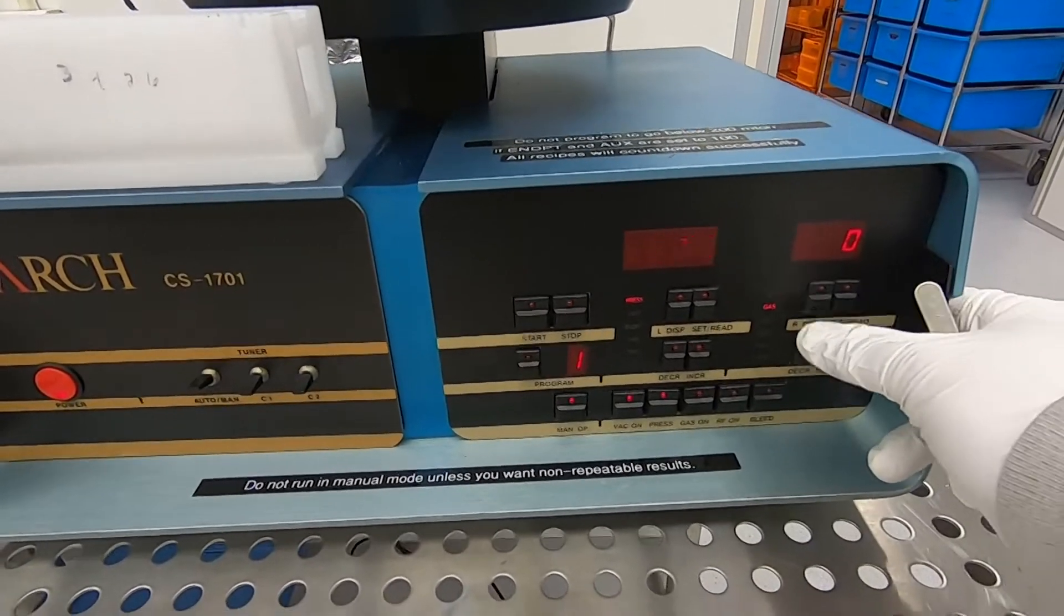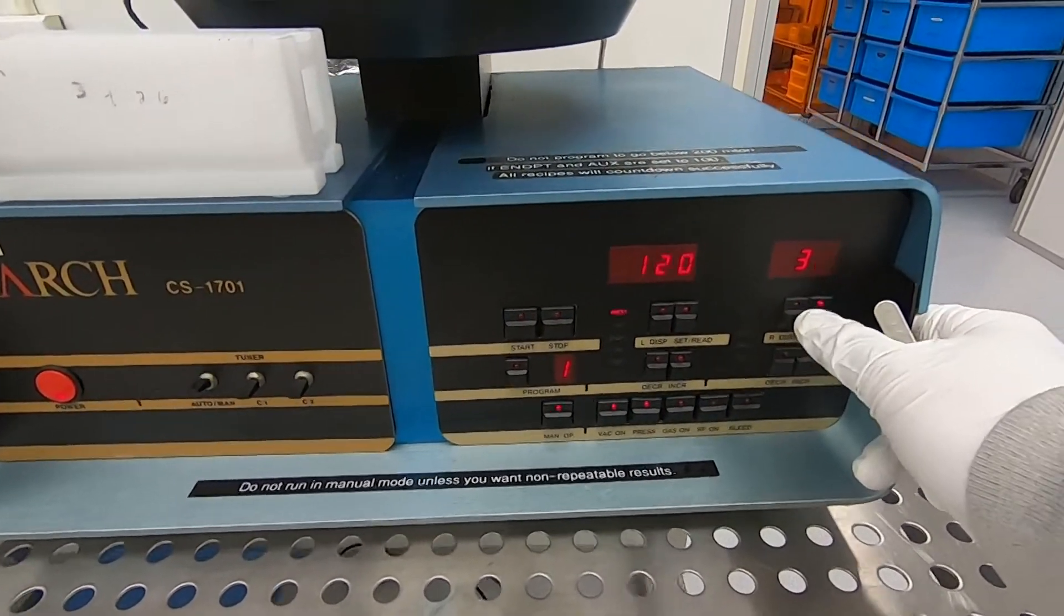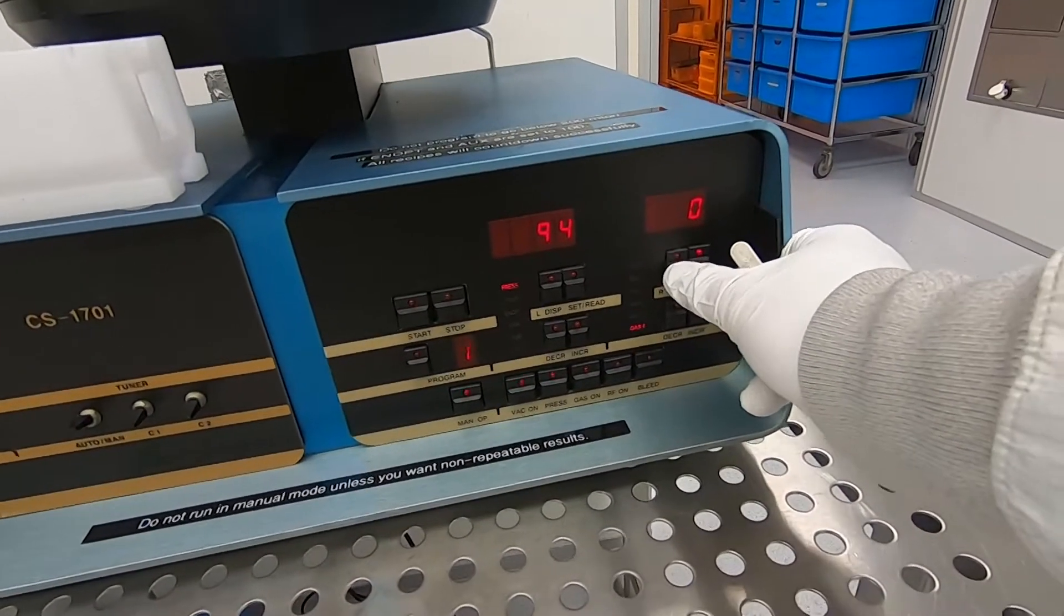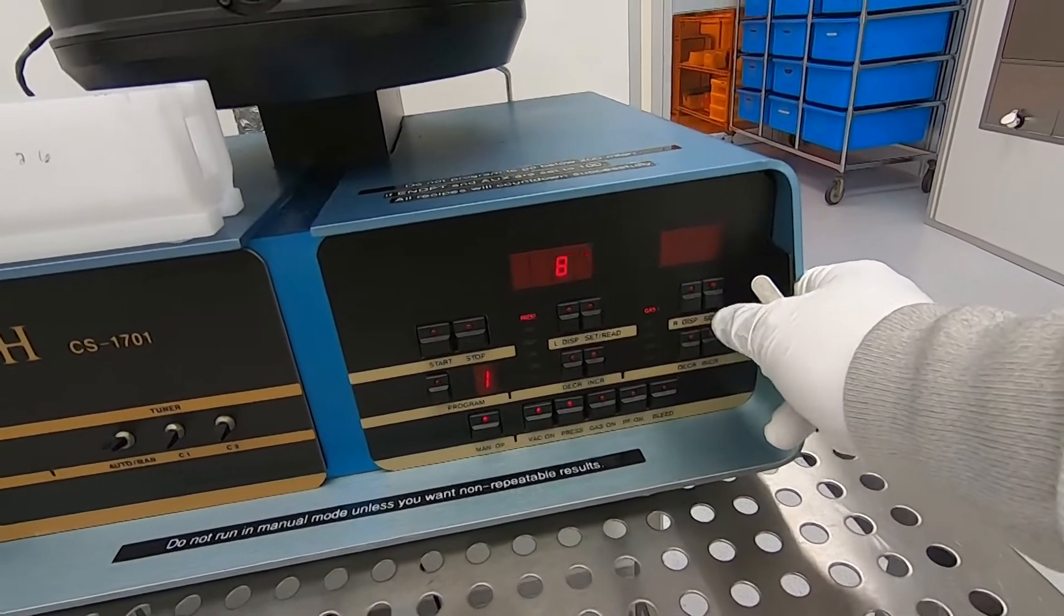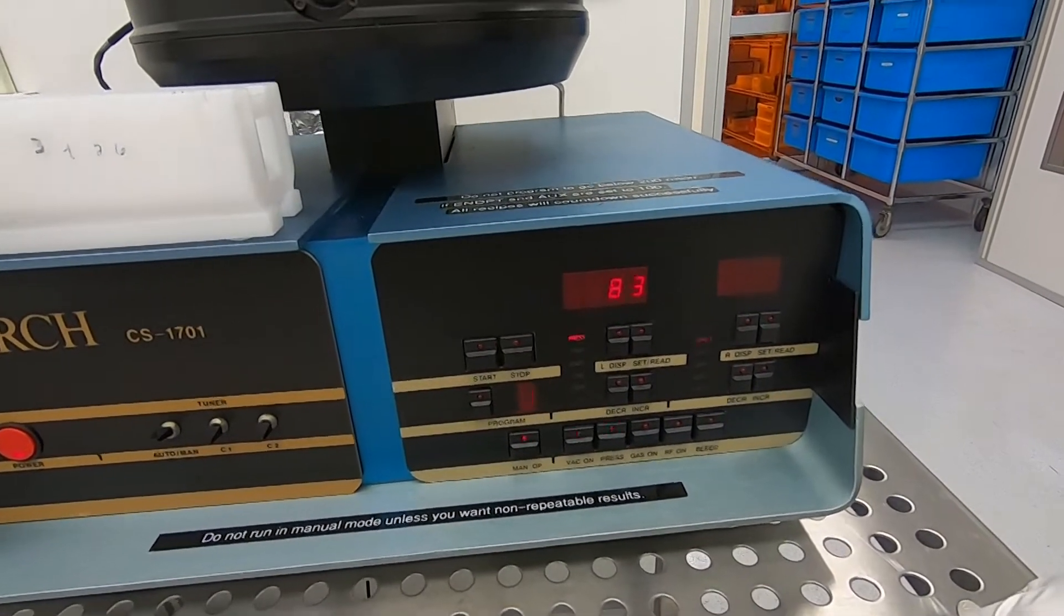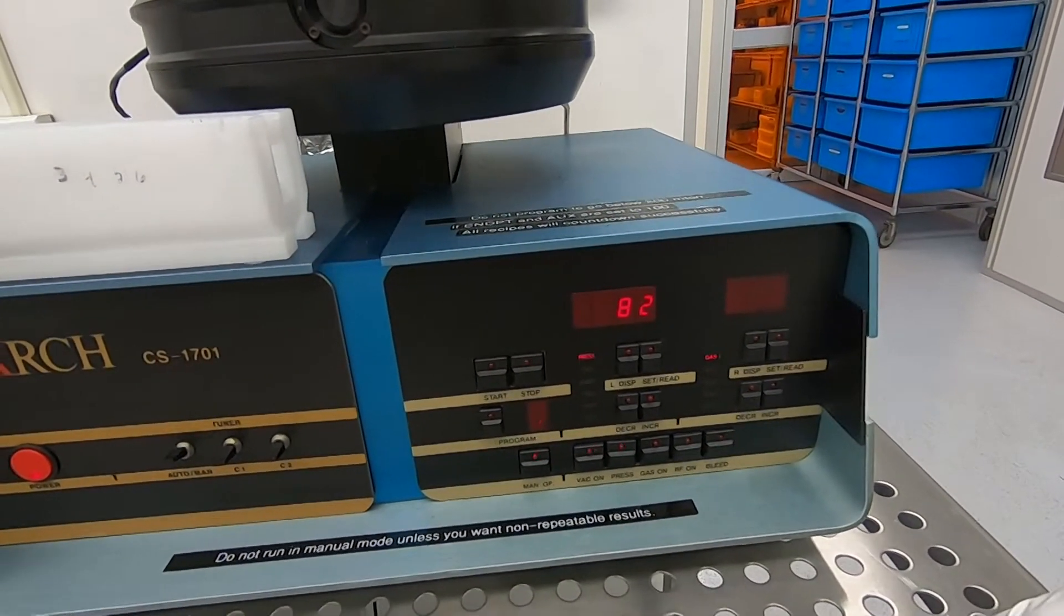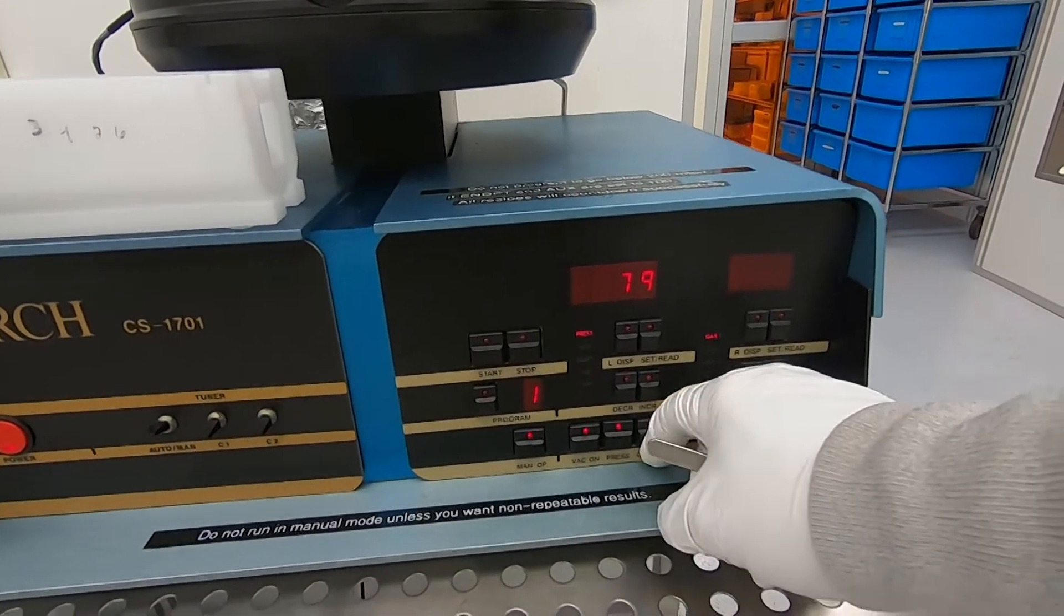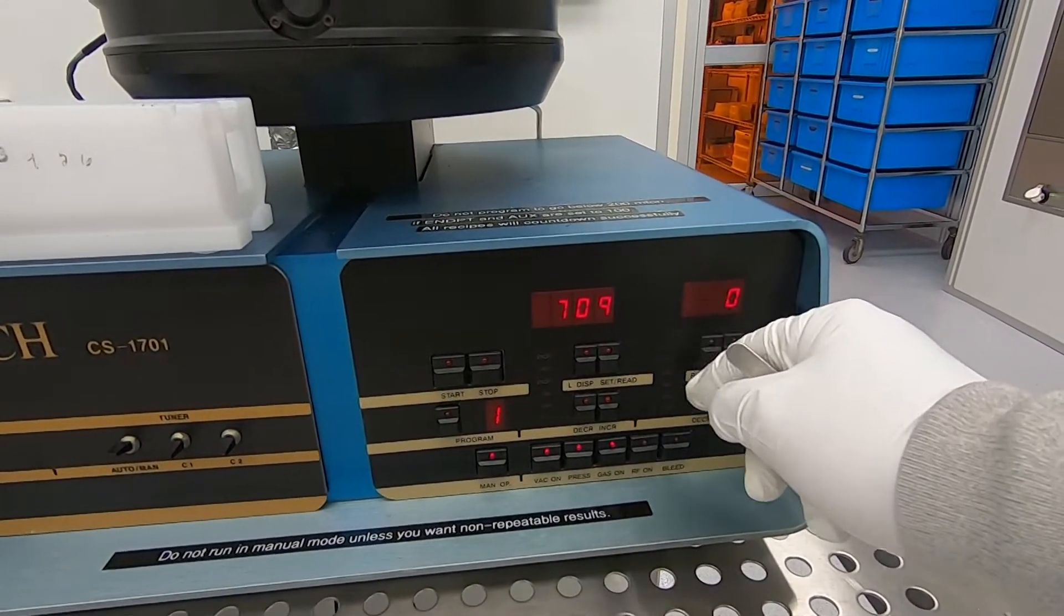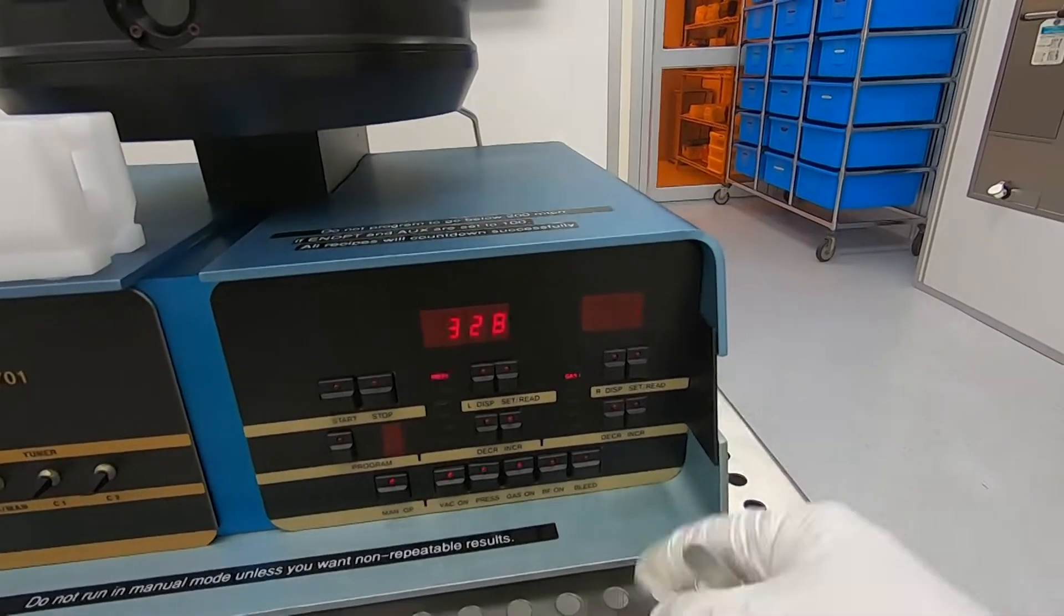While it's pumping down, I'm going to check the flow rates at 30% of full scale on gas two, which is oxygen. All right, so 80 millitorr, that's good enough. Turn the gas on. There's the actual flow rate of the gas.